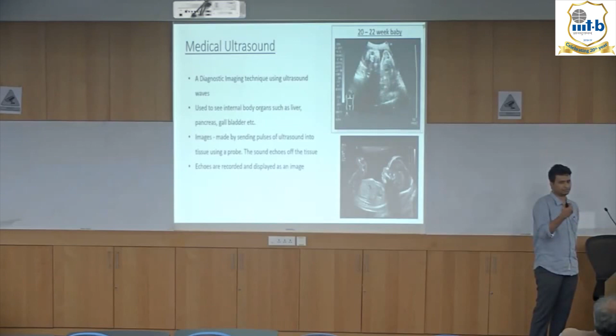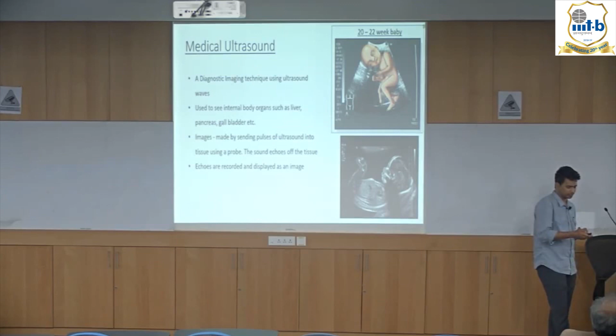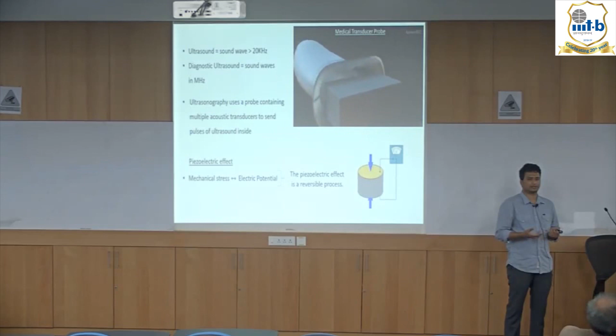It is predominantly used for examining fetal health, for viewing internal organs of the body, like liver, pancreas, and gallbladder. So the ultrasound imaging technique gives real-time images. The real-time images are obtained by sending ultrasound waves into the body, and the tissues in the body echo the sound back. By capturing these echoes and accumulating them, they get displayed as an image. So ultrasound is basically a sound. It's a category of sound waves which have frequencies above 20 kilohertz. Diagnostic ultrasound used for imaging purposes uses sound waves in the frequency range of megahertz.